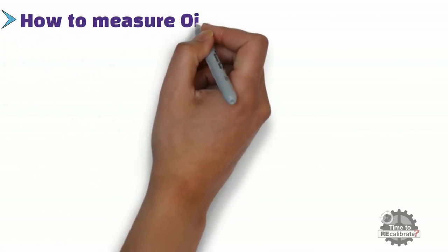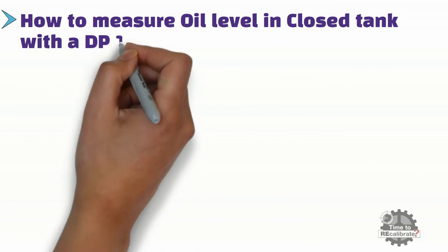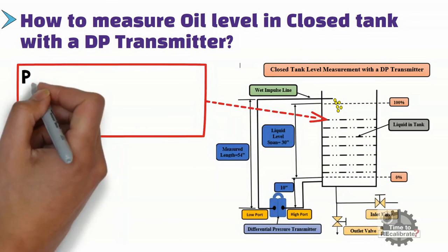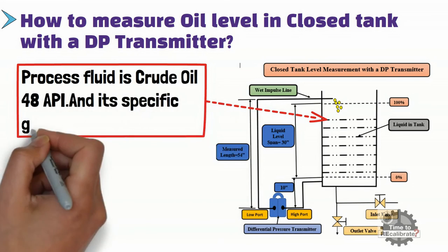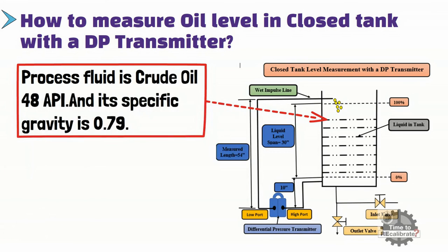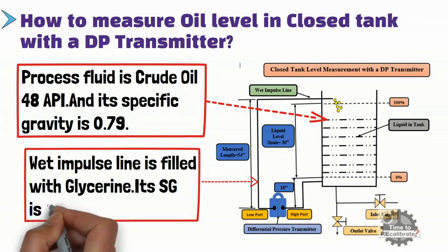Now, how to measure oil level in a closed tank with a DP transmitter? Let's assume that the process fluid is crude oil 48 API in this example, with a specific gravity of 0.79. The wet impulse line is filled with glycerin, and its specific gravity is 1.263. All remaining conditions are the same as the previous example: the DP transmitter is installed 10 inches below the 0% baseline, and the height of the wet impulse line is 54 inches.